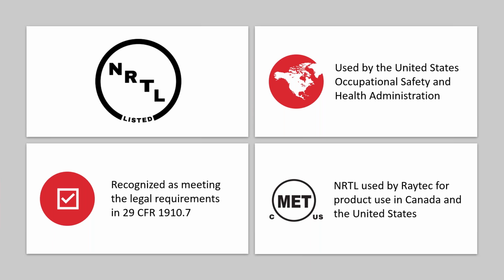So equipment placed on the market in the US and Canada must be tested and certified by a nationally recognized testing laboratory, or NRTL. Now this NRTL ensures compliance with the relevant standards in line with OSHA, which is the Occupational Safety and Health Administration.